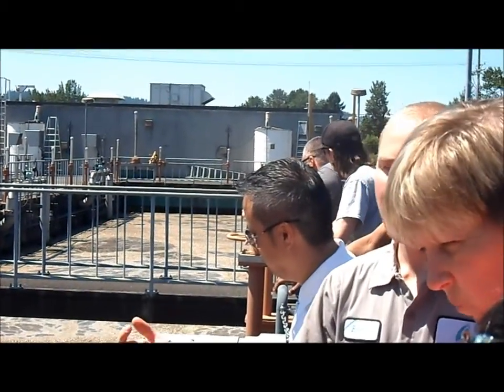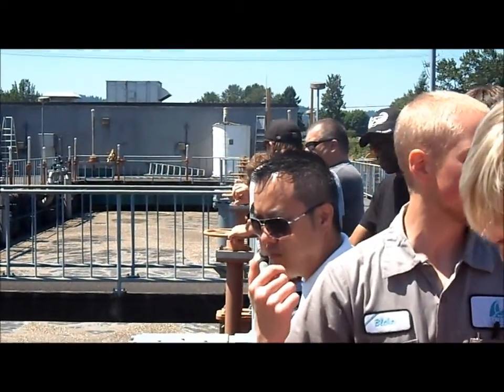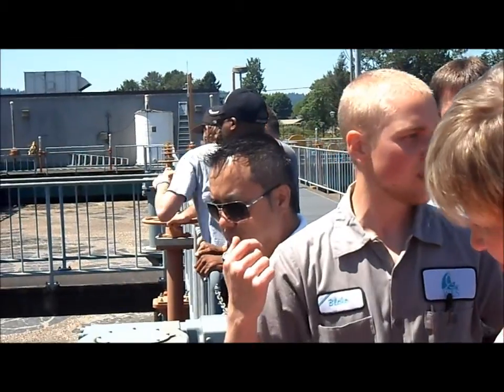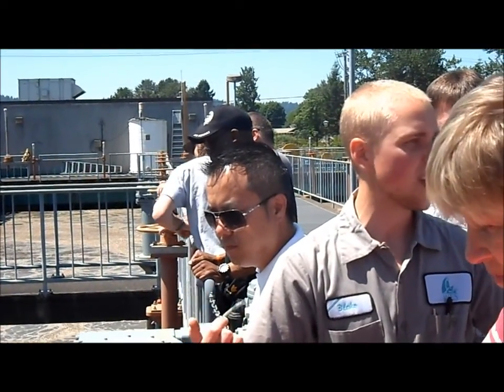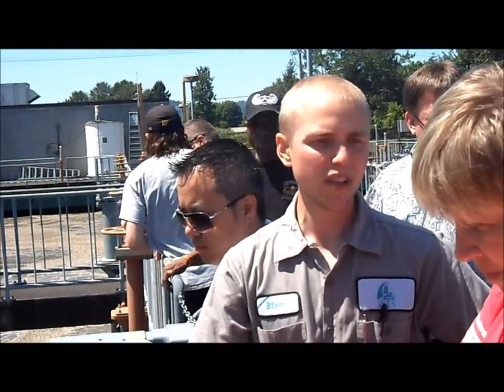No, it's just because we're returning. Our mixed liquor return pumps are doing like 2.5 to 3.5 times the flow. So whatever flow's coming in, we're doing 3 or 3.5 times that. That's why it's just coming up over that wall, plus RAS, plus primary effluent.